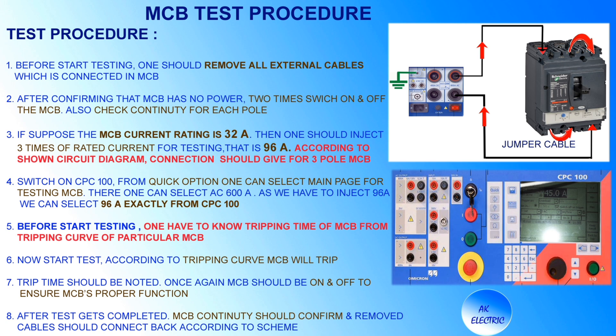Now let's see the MCB testing procedure. Before starting the test, remove all external cables connected to the MCB. After confirming MCB has no power, switch it on and off two times, then check continuity for each pole. If the MCB current rating is 32 ampere, inject three times the rated current for testing — that is 96 ampere. Connection should be given according to the diagram for a 3-pole MCB.